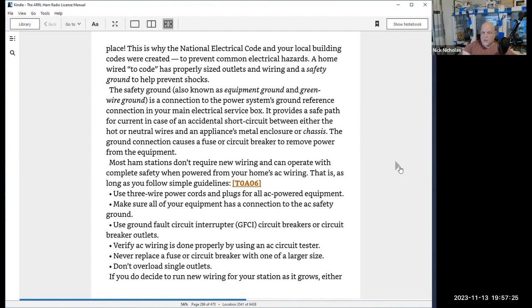Your book tells you not to overload circuits. Wiring in your house is rated for a certain current. For example, in household wiring, number 14 wire is generally rated for 15 amps. Number 12 wire for 20 amps. 30 amps is number 10 wire, and there's a chart you can find on the internet that will get you through even more of them. You exceed that, and the wire can overheat faster than a fuse will blow.